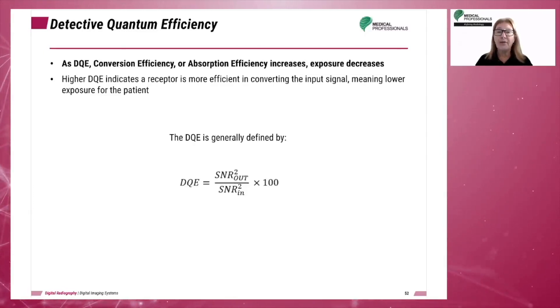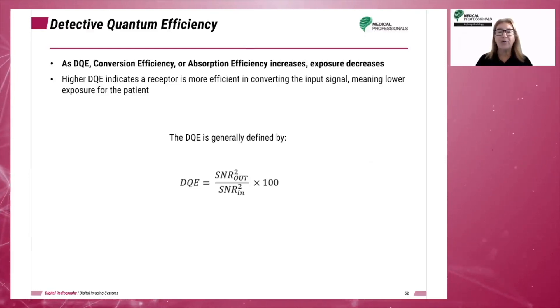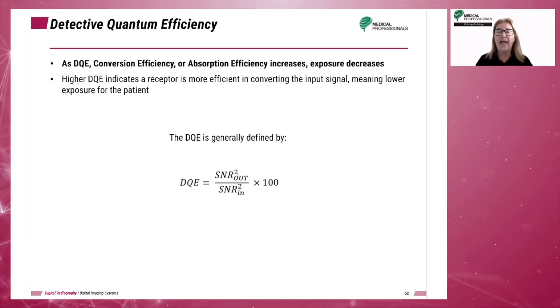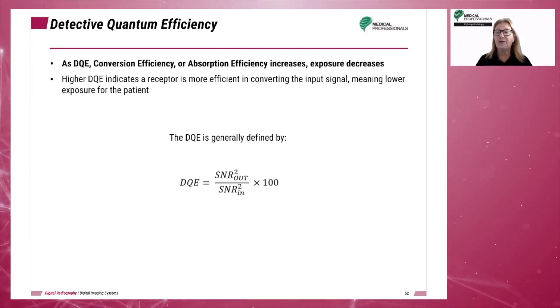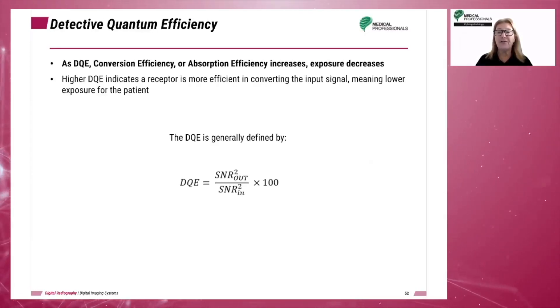Detective quantum efficiency, or DQE, is a measure of the receptor's ability to create an output signal that accurately represents the input signal, or X-ray beam. The image receptor must absorb, convert, and emit efficiently. When placed on a graph of IR materials, you can compare these receptors based on their ability to produce images that exhibit given levels of spatial frequency.